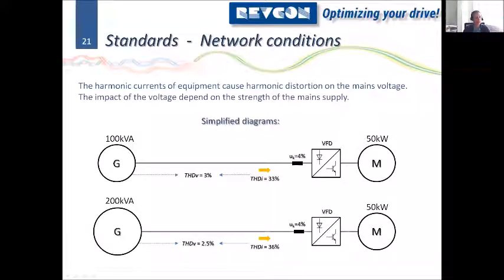So if we look at the first example, if we connect this setup to a 100 kVA generator, we will have a THDI of 33%, and that will result in a THDV of 3%. So the current distortion is 33%, and that will cause a distortion on the voltage and let it go up to 3%. If we take the same drive, the same load, the same motor connected to a stronger 200 kVA generator, that will lead to a higher THDI, but the resulting voltage distortion, THDV, will be only 2.5%. So the stronger your network is, the less voltage distortion you will have.